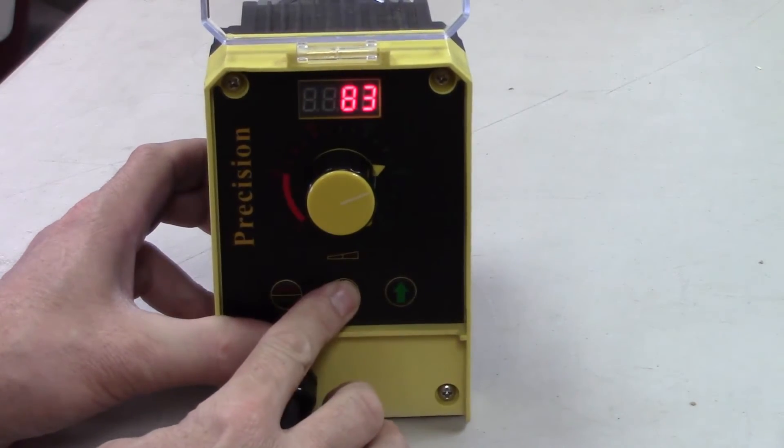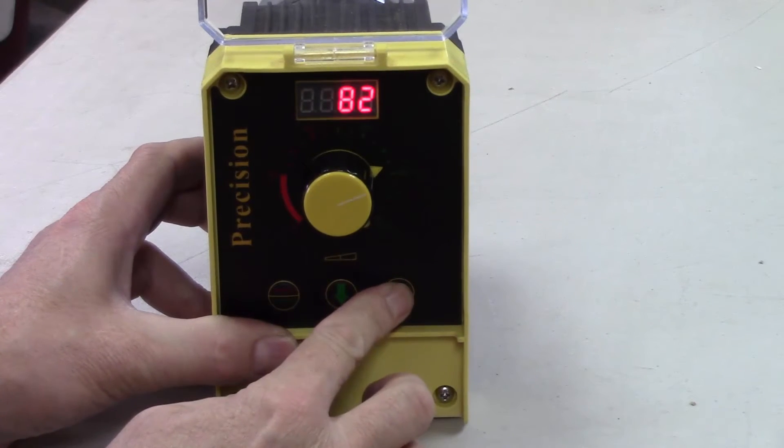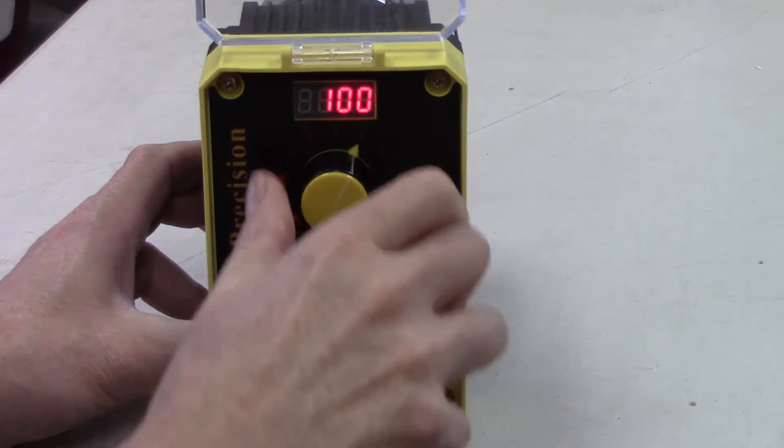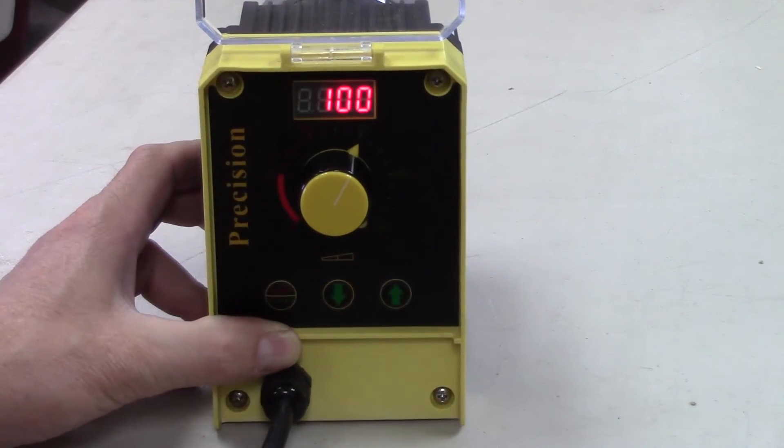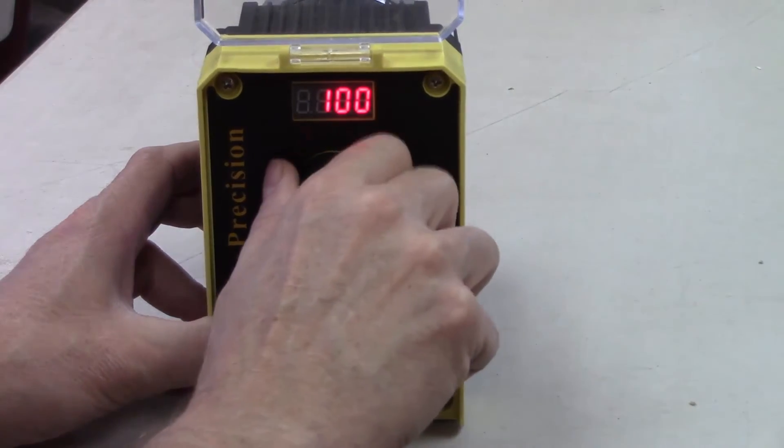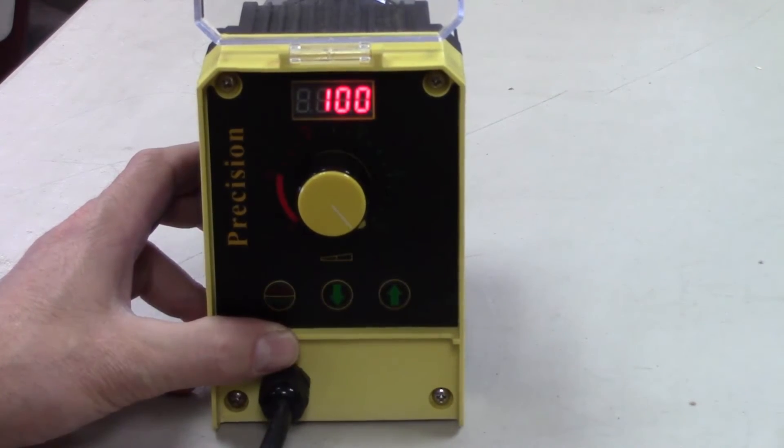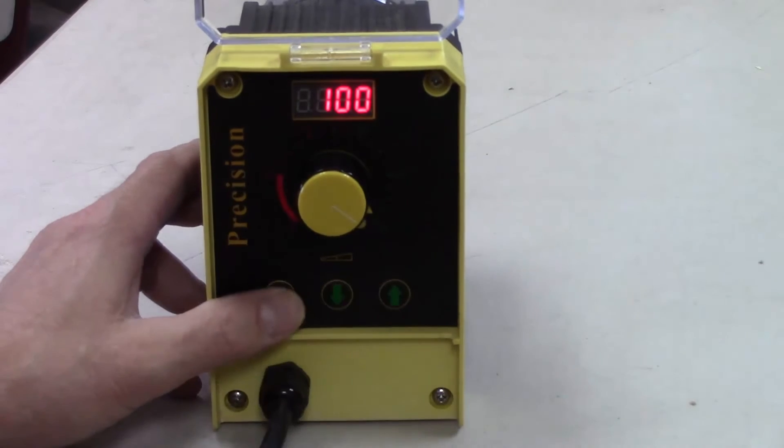So there's at a hundred, and there's at sixty on the dial. That's sixty percent of twenty-four gallons a day is what that would do, and that would be the whole twenty-four gallons a day. It's the maximum output of the pump right there going at a hundred.